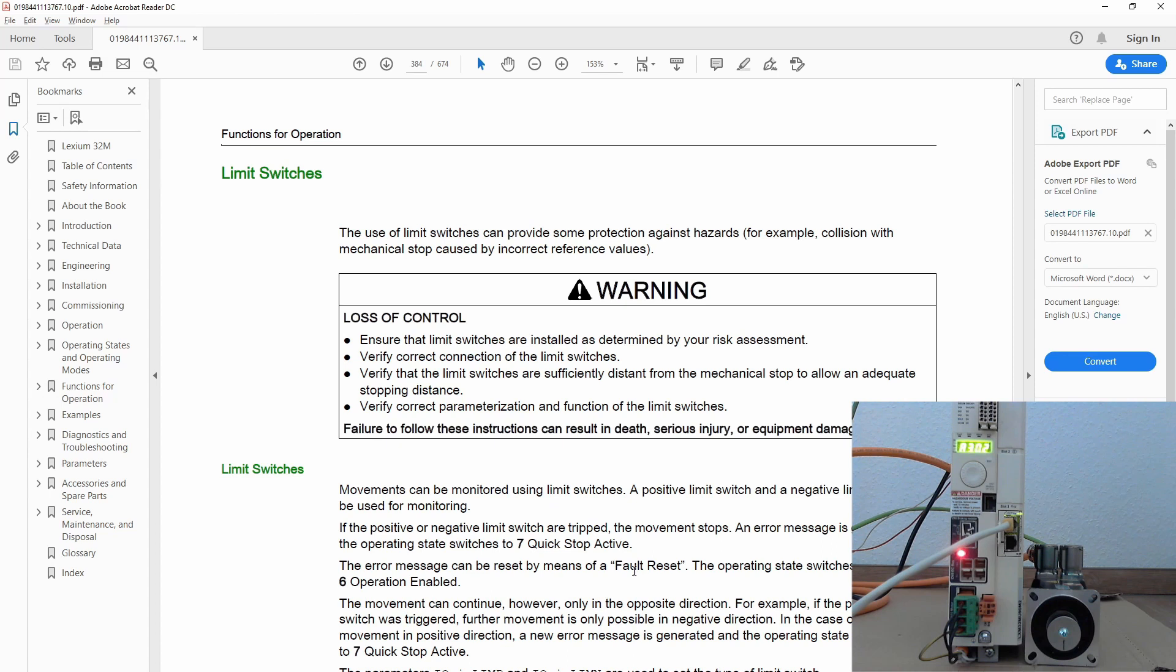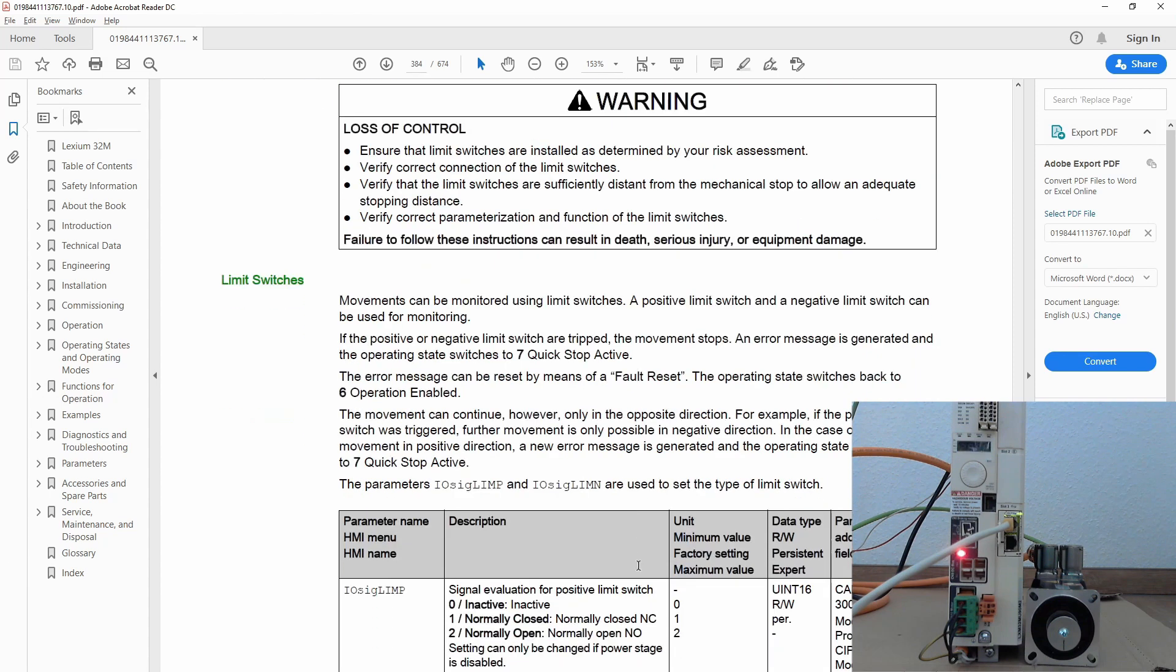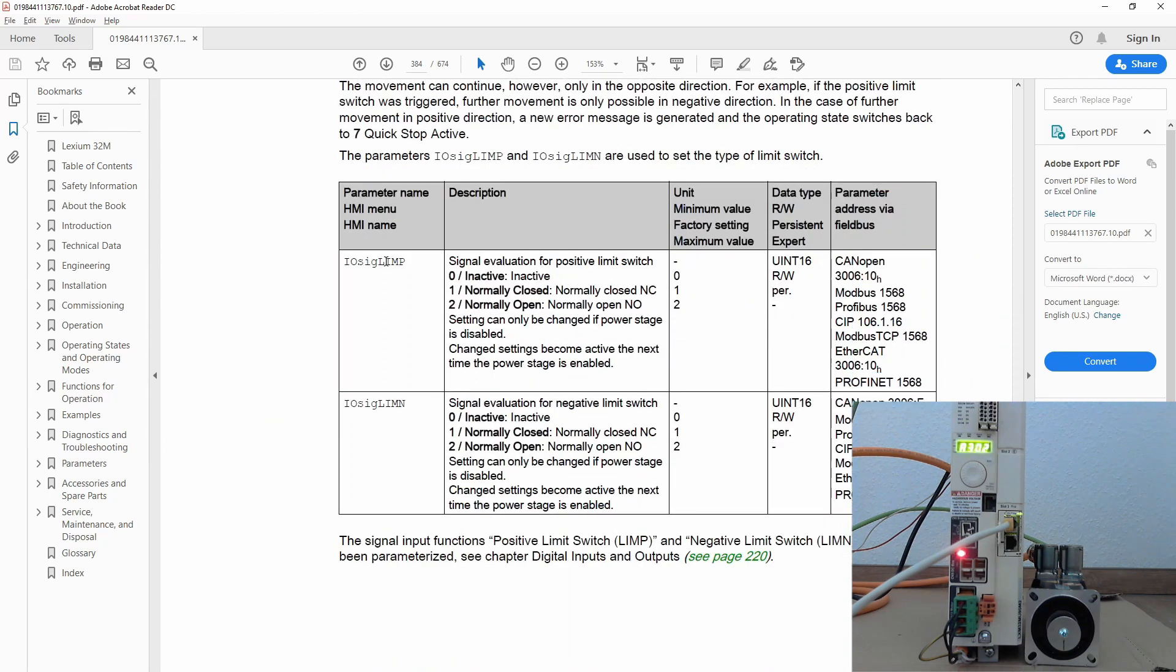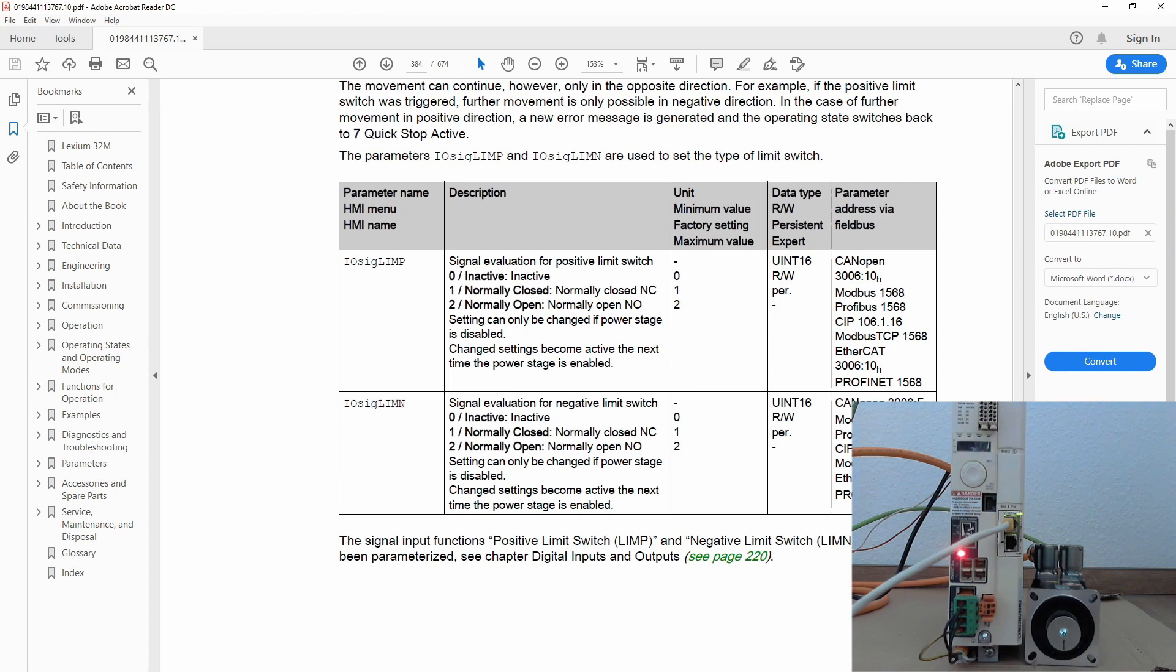You will find limit switch handling for positive and negative limit switch. So main point is to remember this value which is the parameter 3006 for both and subindex 10 and F, and we need to put value 0 to disable both of limit switches.